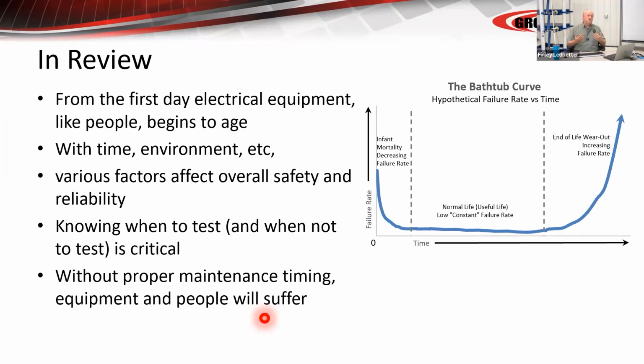You walk into a climate controlled pressurized substation room and you smell something different, you hear something different, any of those sorts of things need to be investigated. And the operators, the electricians that are in these situations, or the technicians that are contractors, need to be aware, and they need to pay attention to these critical telltale signs. It's not always smoke bellowing out of the switchgear or out of the panel. Quite often it just changed tone, it changed frequency, something got loose, the sound changed, temperature went up a few degrees. Sometimes it's a smell. You can smell when older organic insulation starts to get hot. It's a definite smell to it. When it starts to release some of the material and release a smell when the varnishes start to cook, you'll smell it.